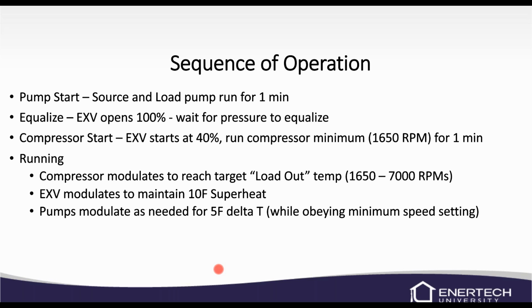After that, the compressor is going to modulate to reach target load-out temperature, and when you look at the main screen, it'll give you a range based on your heat curve of what your RPM range is. It may be 1,650 to 5,000 or 1,650 to 6,500. It just depends, but it will modulate to reach that temp. It'll probably ramp up pretty quickly on initial startup. The EXV will then modulate to try to maintain 10 degrees of superheat, and the pumps will modulate to try to maintain 5 degrees delta T.